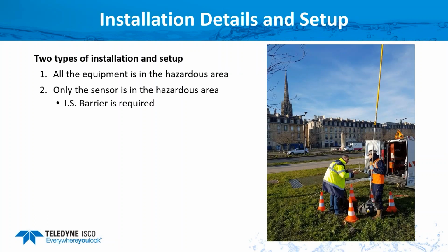Now let's go over some of the installation details and setup. There are two types of installations and setup. One is where all the equipment is located in the hazardous area. So your logger, your sensor, everything must be IS rated. Or the sensor is in the hazardous area, but then you keep your electronics in the safe area, which would be separated by an IS barrier, which I'll show you some examples of in just a minute.